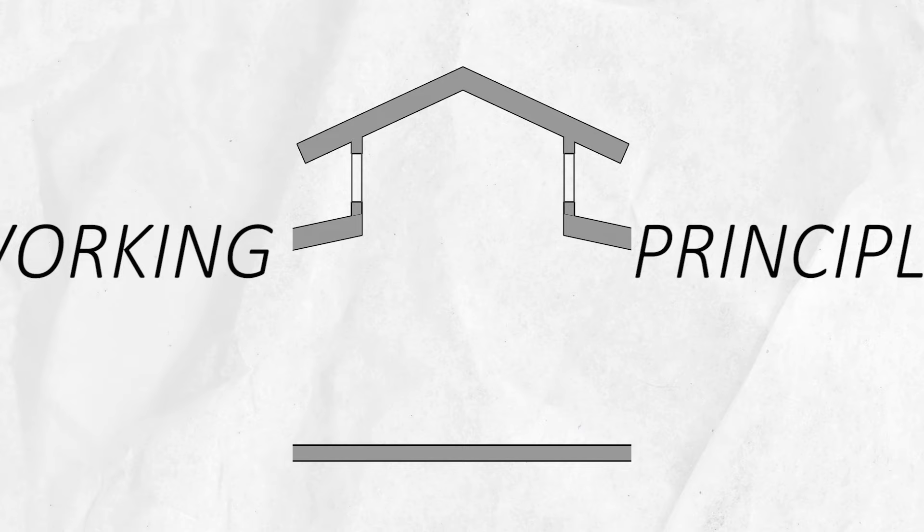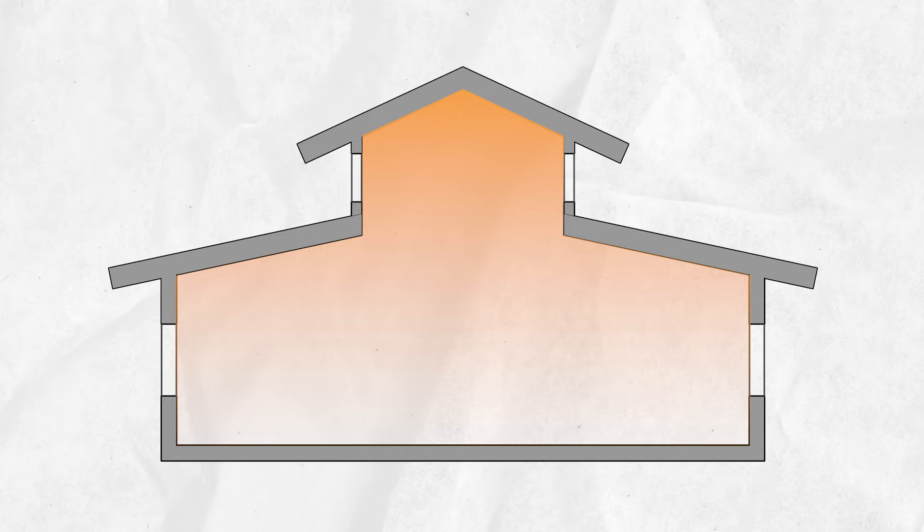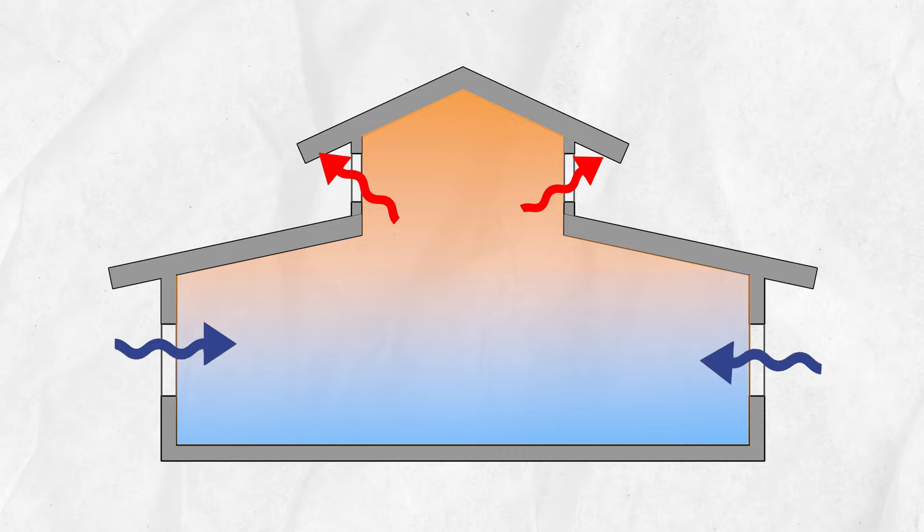The principle of natural ventilation is based on the stack effect. When the temperature goes up inside the room, the air heats up and becomes hot air, which goes upward because hot air is lighter. It tries to escape from the opening in higher places, and the vacant space is replaced by cool air coming from the windward side opening.